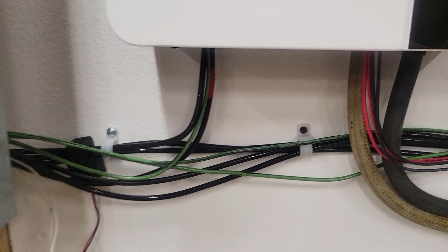That is one of the benefits of using the 240 volt inverters. Growatt, as well as several other brands out there, such as SMA, make inverters that put out 120 volts only. If you want to combine them to create split phase for your house, you need them in pairs, so they'll be 120 and 120 out of phase of each other, making 240 volts across both of them. That works fine, but when you need more than what just 2 inverters can put out, you always need to jump up in pairs. Sometimes that doesn't work out to your benefit, and other times it just might not be a big deal at all.